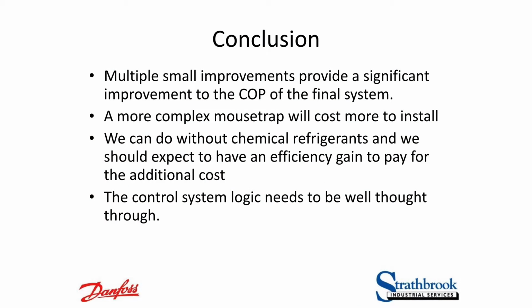We haven't had the thing running long enough to know, but without it being in Melbourne where it's colder and it'll behave better anyway, just this plant compared to the other plants, had they been in the same location, we're expecting sort of 5 to 10% gain again over the previous effort. So the conclusion from all this is that multiple small improvements provided a significant COP gain by the time we got to the last plant, but it is a more complex thing.